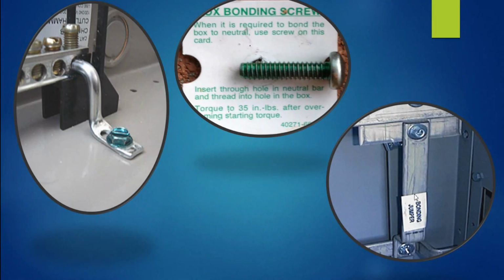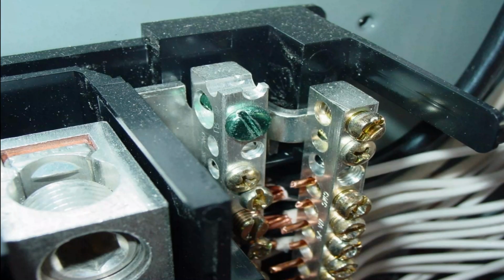So here are some representations of the main bonding jumpers that you might see within different service equipment that you might encounter. Here's an example of the screw actually being put into a piece of equipment, and it's a threaded entry. You can't see it behind here, but here's an example of a hole. It might be threaded, and the screw screws right into it. Many times this is loose or not even screwed in, so you do have to make sure it's in. And again, it does have torquing requirements.